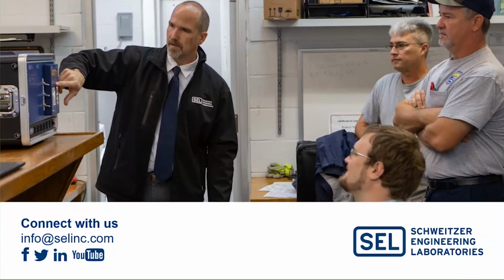So I came on site, powered it up, and pulled the SER out of it. I said, do you want to know what happened? We walked through it: the button was pushed at this time, the high level alarm went off here, they went out and put it in hand and pumped the station down. They couldn't figure out why it wouldn't operate in auto, and then they ended up taking it out of service. So it allowed us to say, oh man, we should have just given you guys a call. I didn't realize that happened.